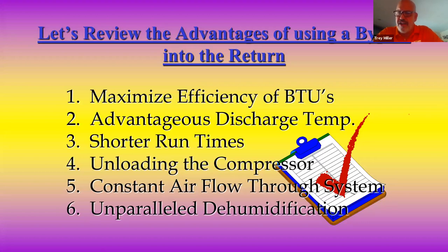And guys, unparalleled dehumidification. This is huge. One thing I highly recommend, when you put this in retrofit, which you will sooner or later, make sure you blow out your drain line. Make sure you change the P-trap. The mud daubers that have climbed in there and built that, there is no more drip from your drain line. You've got a steady stream of water pouring out, guys. We're getting rid of a lot more moisture, and this is the key to an efficient system and to comfort.